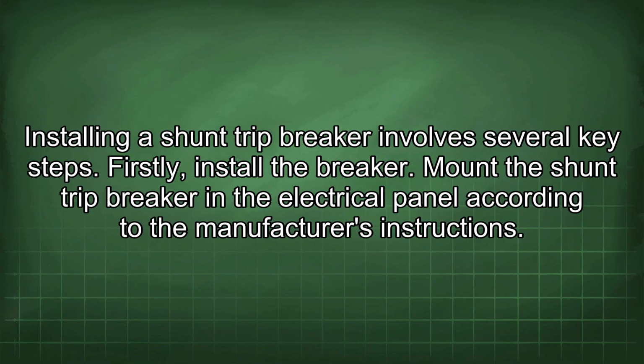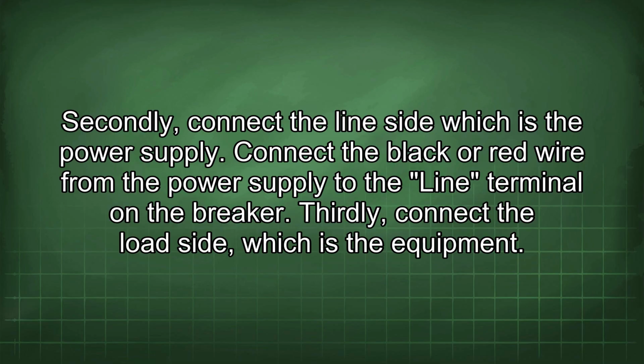Installing a shunt trip breaker involves several key steps. Firstly, install the breaker. Mount the shunt trip breaker in the electrical panel according to the manufacturer's instructions. Secondly, connect the line side, which is the power supply. Connect the black or red wire from the power supply to the line terminal on the breaker.